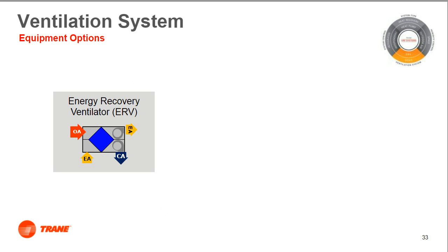Energy recovery ventilators are an inexpensive method for providing either direct-to-space or direct-to-terminal zone unit method of providing conditioned outside air. An energy recovery ventilator uses an air-to-air heat exchanger to precondition the outside air by exchanging heat and sometimes moisture with the exhaust air stream. There are no cooling or heating coils used to precisely condition the ventilation air to an exact temperature or dew point. So, in most climates, there will be times during the cooling season when the unit supplies conditioned ventilation air hotter and or wetter than the space set point. And there will be times during the heating season when the unit supplies air colder than the space heating set point temperature.